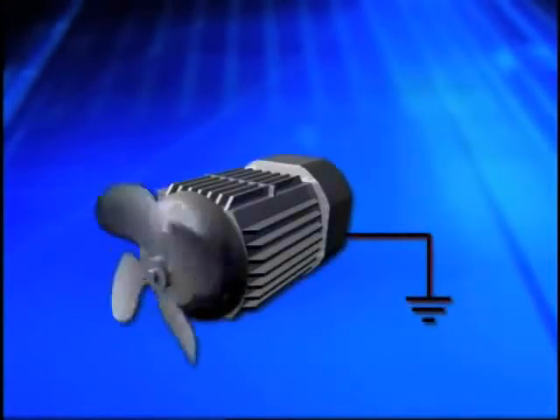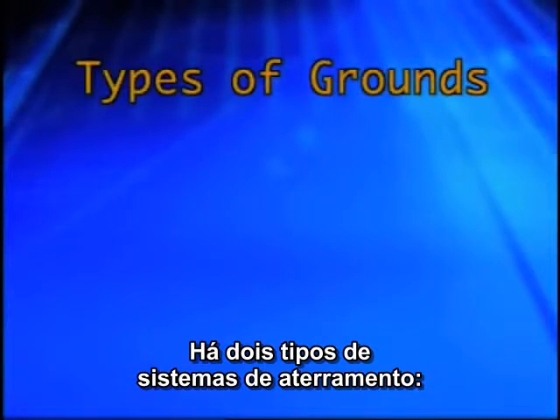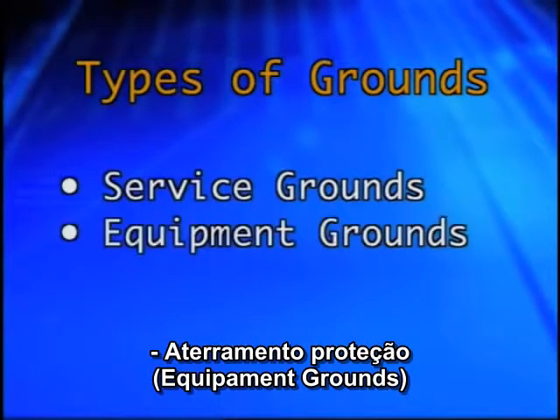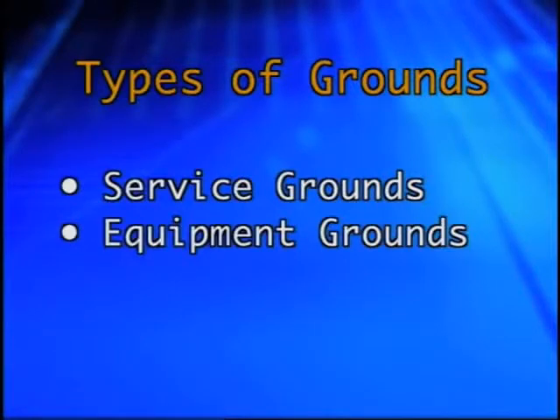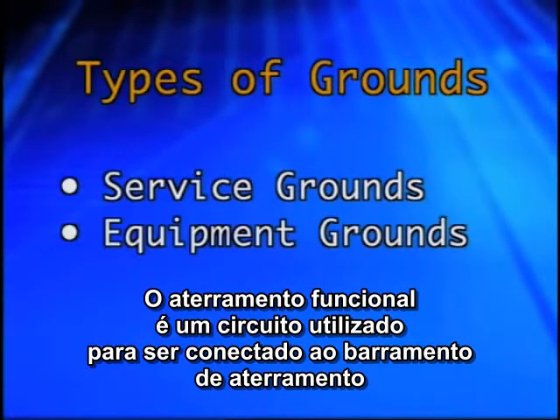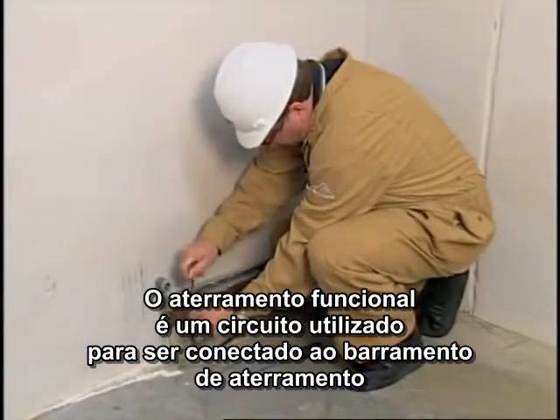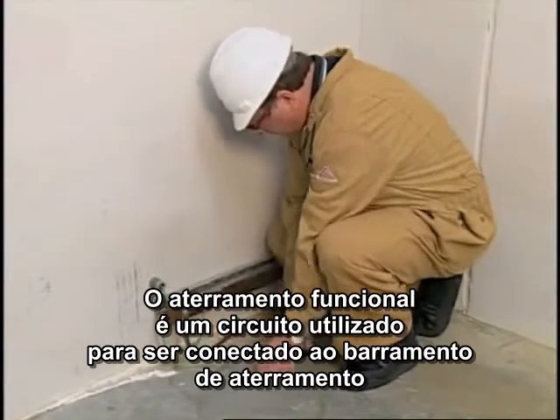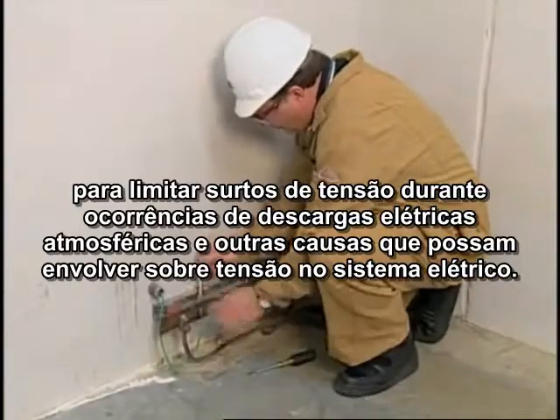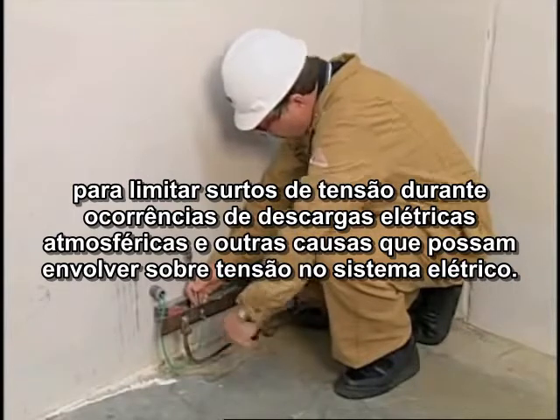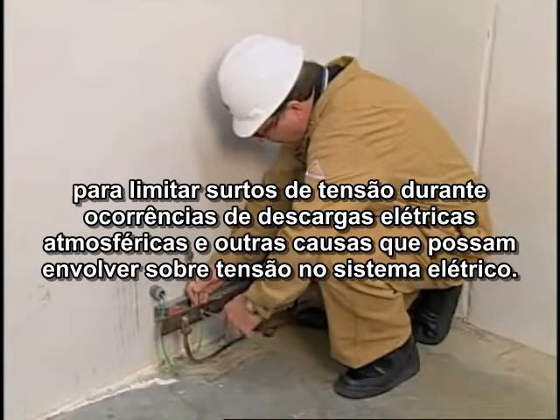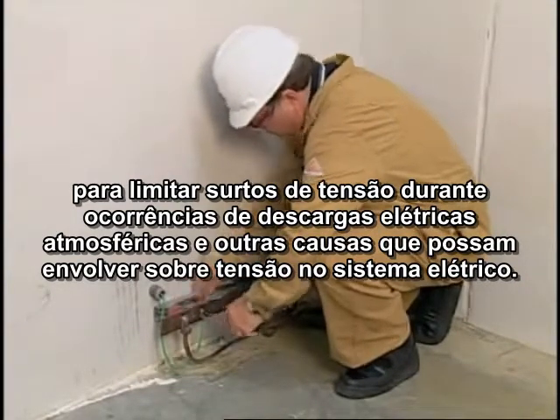intact. There are two types of grounds or ground systems: service grounds and equipment grounds. Each has a specific purpose. A service ground is the grounding of one conductor of the system to a ground electrode. Service grounds limit voltage surges from lightning strikes and other causes that may impose a high voltage condition on the system.